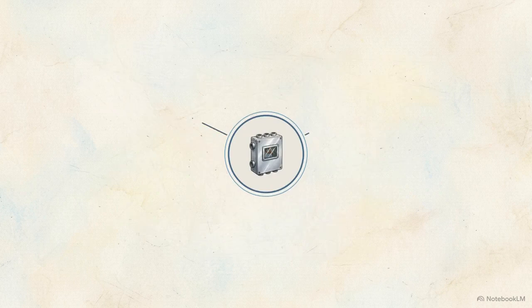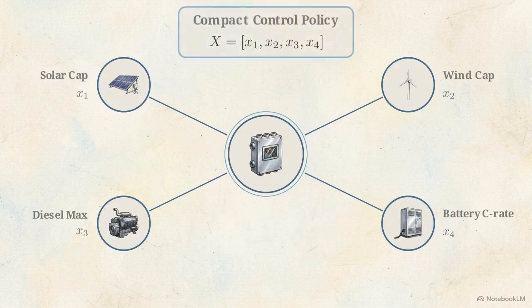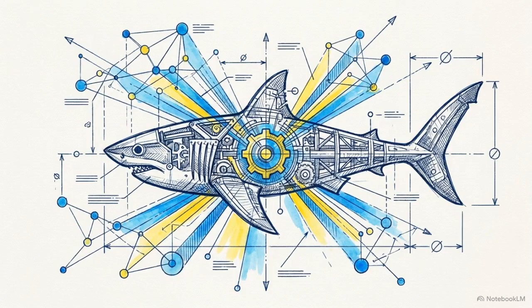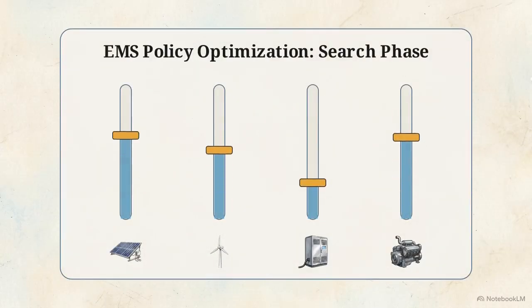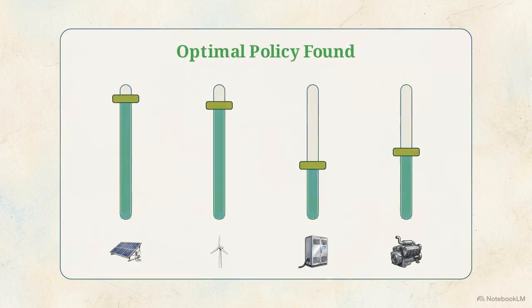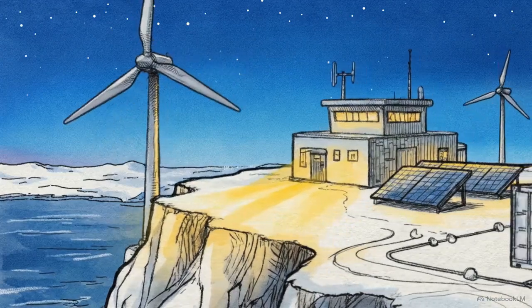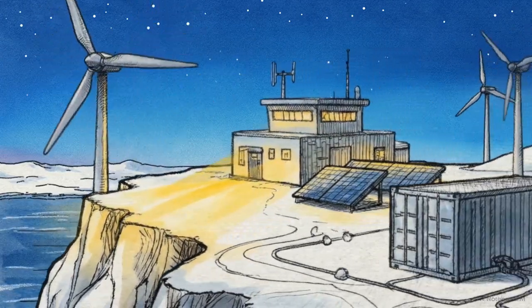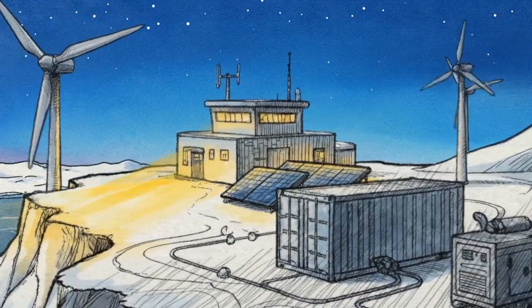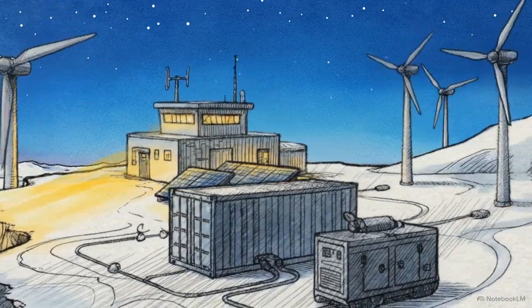Instead of a massive neural network, this system relies on a highly compact control policy driven by exactly 4 operational parameters. To tune those parameters, it uses a metaheuristic optimization engine called the marine predators algorithm. This algorithm evaluates the hardware limits and continually searches for the most efficient parameter combination to adjust the grid's output on the fly. The result is a transparent, controller-ready mathematical model that balances the power load instantly without sacrificing reliability.